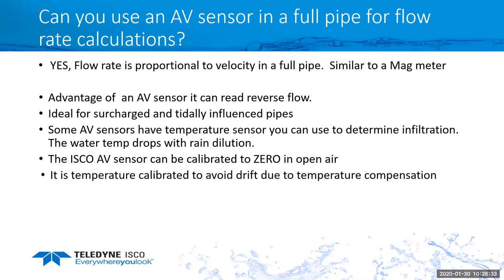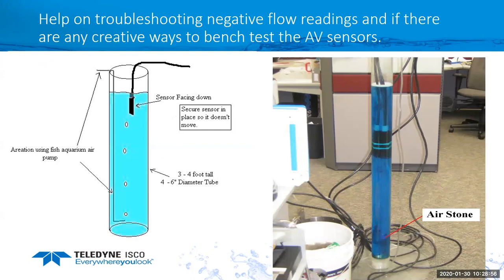As far as our sensors being temperature calibrated, the idea behind this is to avoid drift due to compensation. Sensors that don't have it would require you to take the sensor, put it in the water for 5 to 10 minutes to let it acclimate to the water temperature, and then calibrate your level. If you didn't do this, then you put it in, you would actually see a level shift due to the temperature.